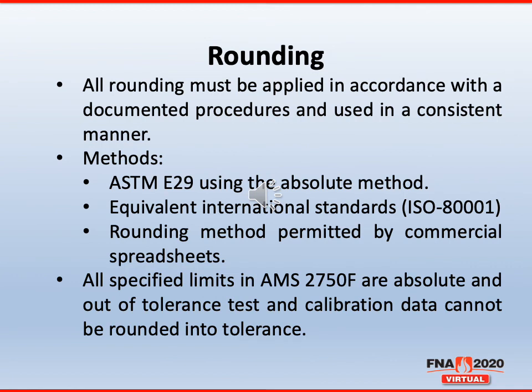So everyone's favorite topic in AMS 2750 when it came out in Rev E was rounding. And we finally addressed rounding in Rev F with a little more clarity and better understanding. First off, all rounding must be applied in accordance with a documented procedure and used in a consistent manner. So you are allowed three different methods of rounding: ASTM E29 using the absolute method, or an equivalent international standard such as ISO 80000-1 Rule B, or you're allowed to round per any commercial spreadsheet. So the way we learned in school, where 0.5 rounds up, as done by a commercial spreadsheet, we are allowing that as long as this is documented in a procedure and always used in that consistent manner.